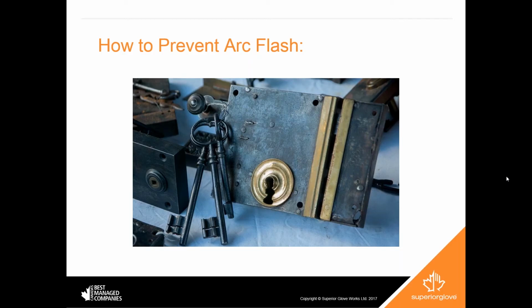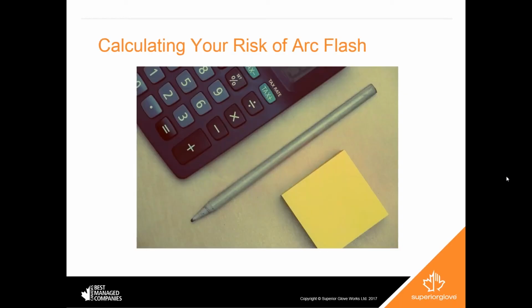So your general maintenance will be to use a proper lockout tag out program. There are certainly guided procedures and many ways of doing this that meet the OSHA regulations. One of the other pieces, as you're following your proper lockout and tag out, is to double check and take a voltage reading once you're in the machine or in the part of the machine that you might be working in, and make sure that you have properly locked everything out and de-energized the piece of equipment that you're working on. Matt?